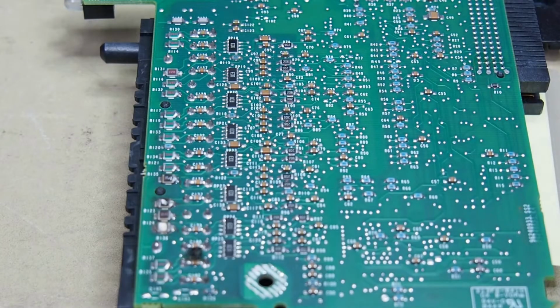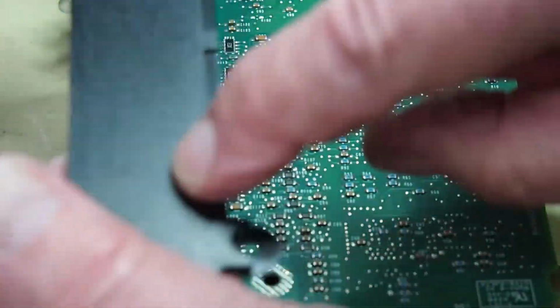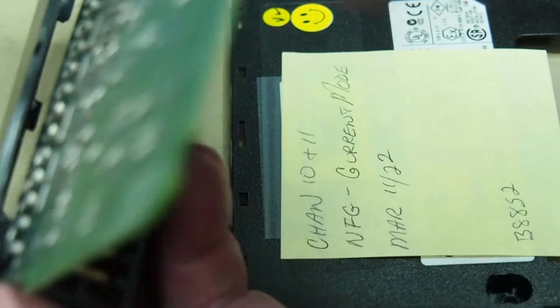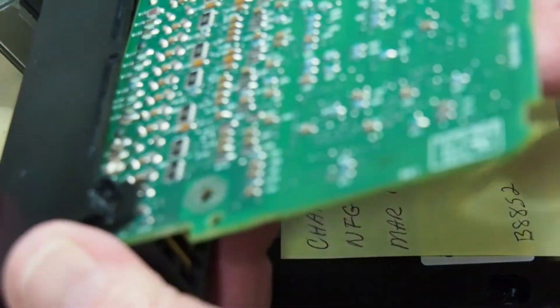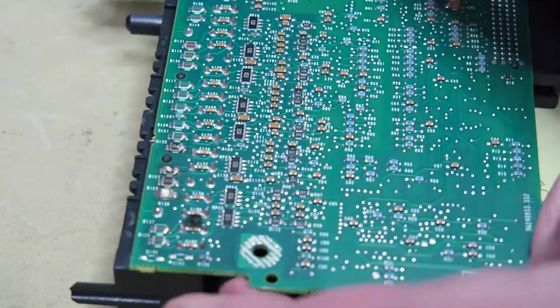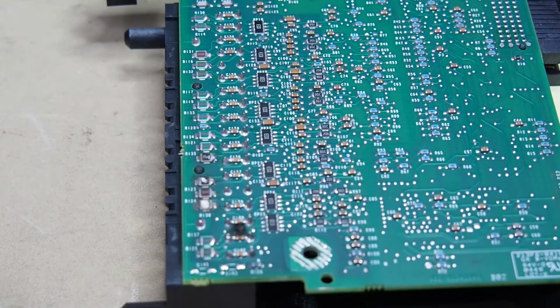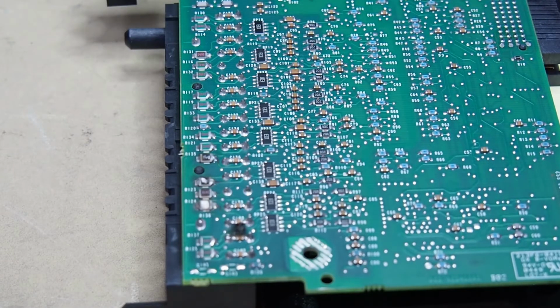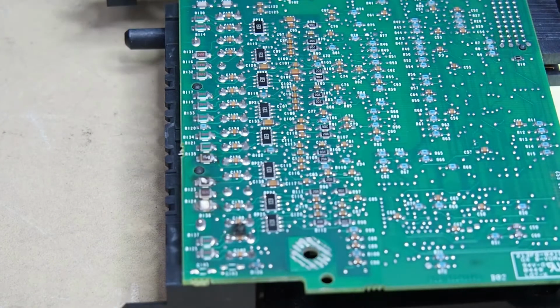So where this resides is underneath this little piece here, and unless you'd had the side plates off and looked underneath there, you wouldn't have seen that. So you have to take the side plate off to check that. But if we had not tested in both modes, voltage and current, we wouldn't have found that. And if I had sold this to a customer and they wanted to use it on current mode, I would have been doing warranty. So there we go. There's a prime example of why you need to be testing everything fully and using all of the components on the card. And that's where your single-ended current and single-ended voltage will show you what's going on.